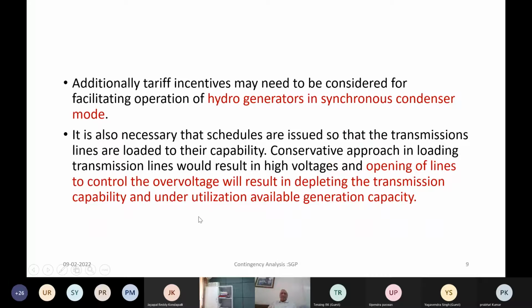So this is where an additional tariff incentive may need to be considered for facilitating operation of hydro generators in synchronous condenser mode. We discussed yesterday what modifications are required to enable synchronous condenser operation. If a new plant of more than 50 megawatt capacity is being built, then the technical standard now mandates that synchronous condenser capacity should be designed. Even the old powerhouses can be retrofitted to enable this operation with the necessary modifications.